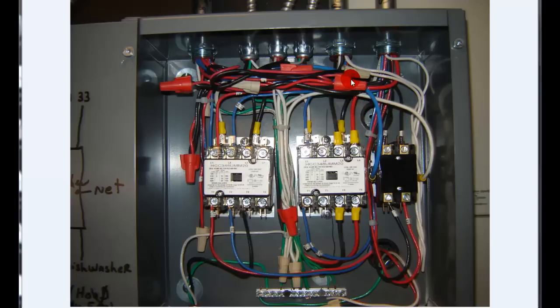You've got your lines, your loads, your control voltages. You've got to have a power source coming from your panel back through, so that if the suppression system is activated, it'll send the power back to the shunt trip breaker and trip that off too.